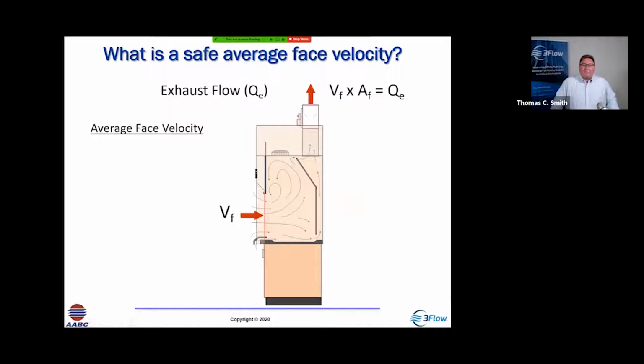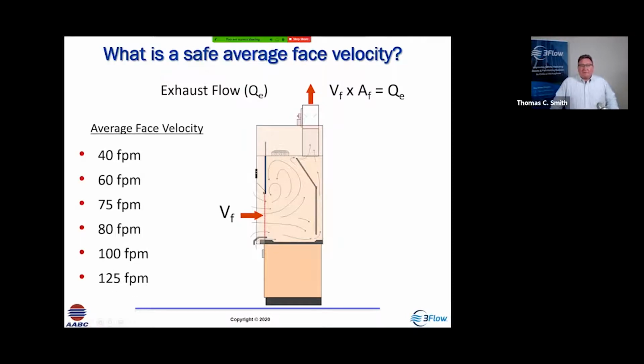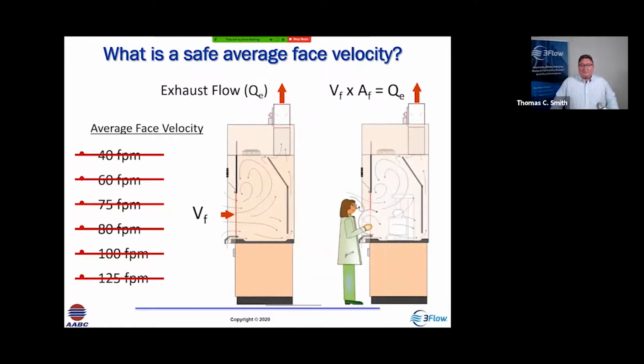But here's the question. What is the safe average face velocity? So you might be answering that question yourselves. Let me give you a little bit of help. Is it 40 feet per minute or 60 feet per minute or 100 feet per minute? What's the safe average face velocity? Well, as it turns out, there is no safe average face velocity. The face velocity has to be appropriate to protect the person.